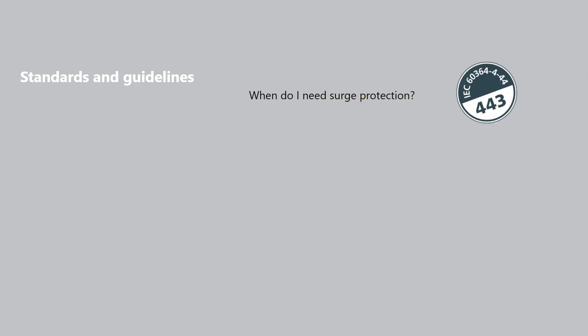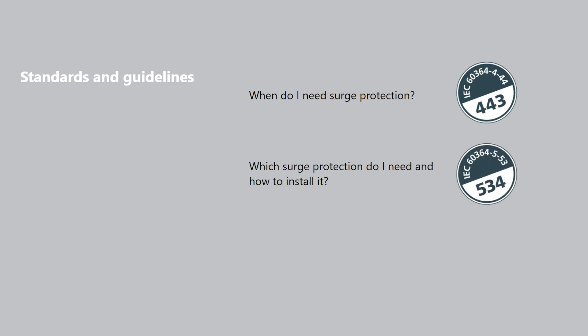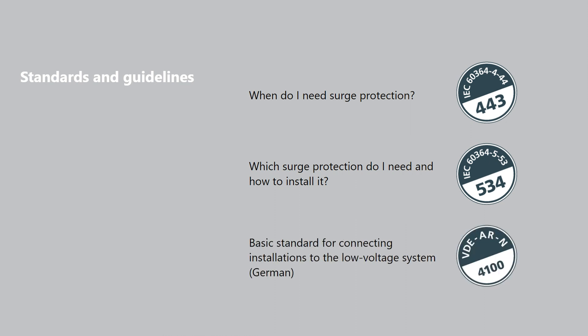The IEC 60364-4-44 clause 443 and IEC 60364-5-53 clause 534 standards provide answers to the following questions: when do I need surge protection, what type should I select, and where should I install it? In addition, the German VDE-AR-N 4100 guideline for connecting installations to the low voltage system should be observed. It describes the relevant requirements for using type 1 arresters in the main power supply system.